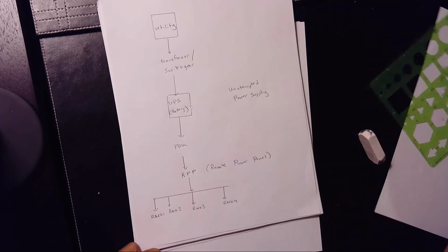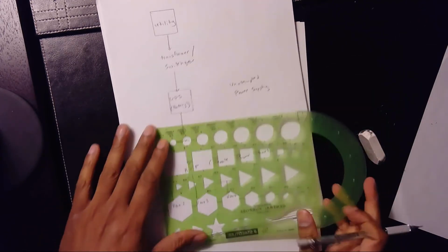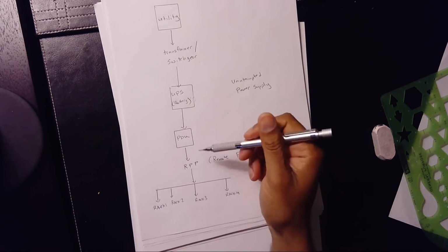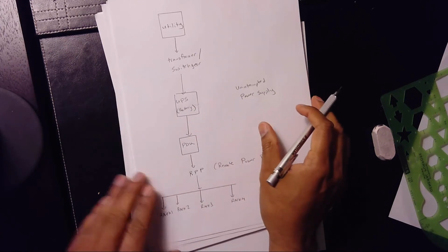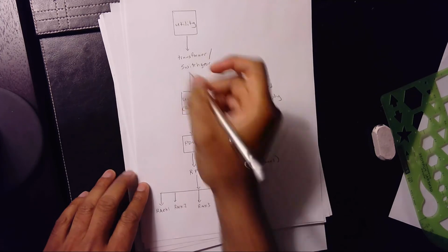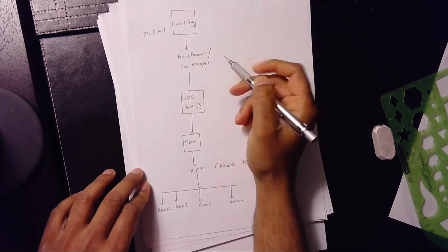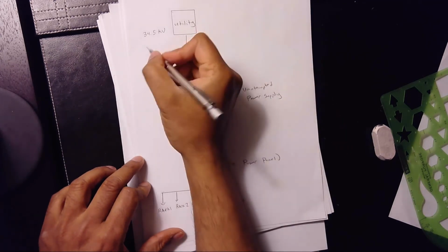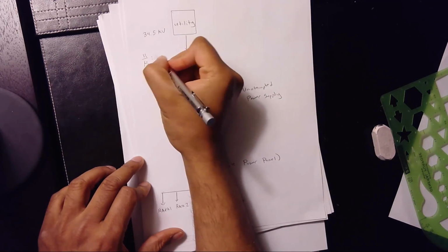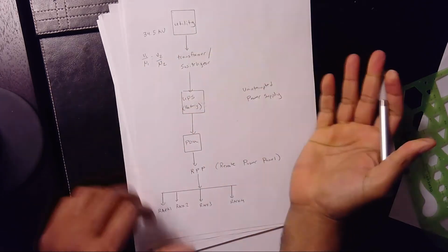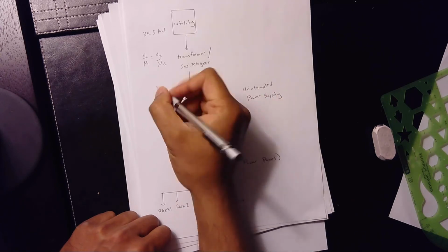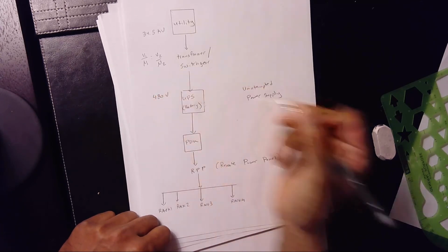And obviously, I want to put a box around our PDU. Our focus is really going to be, when we talk about double conversion, we're going to stick with this area in a little bit. So understand how the power drops are working. Our utility is roughly 34.5 kV. It goes through a transformation, which is V1 over N1 equals V2 over N2. We covered that previously. Our UPS, the transformation resulting from here to here, is 480 volts.